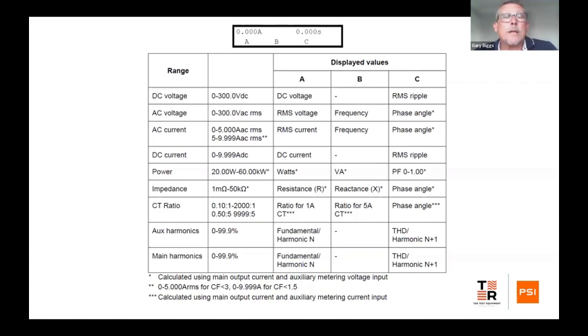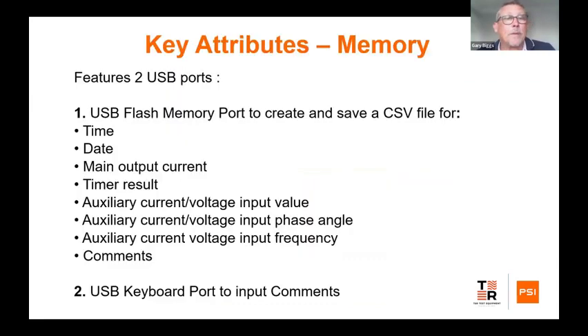And this would just give you an indication of the values, the multimeter specification that's built into the relay test set. Another aspect that we've got on our test sets that differs from many of our competitors is we have two USB ports. The first USB port is a memory flash drive, and it stores the data to a CSV file.